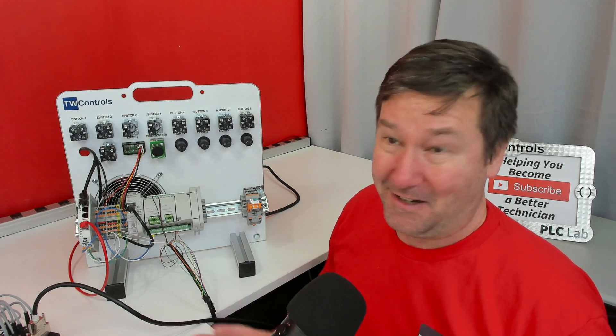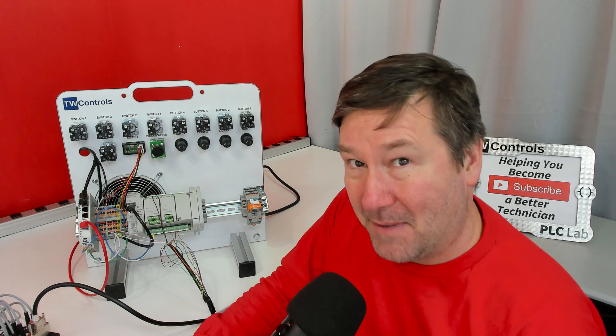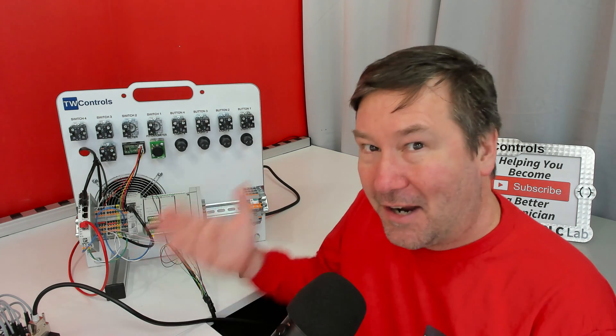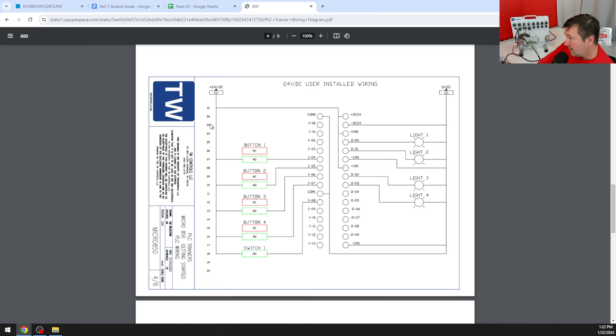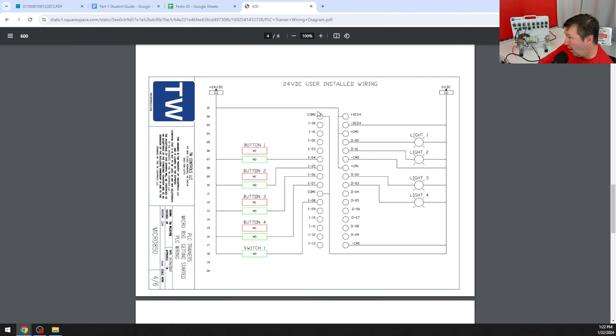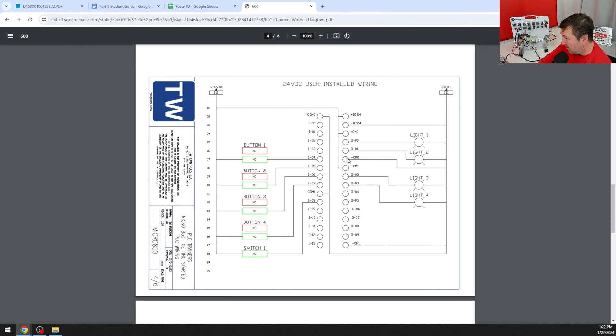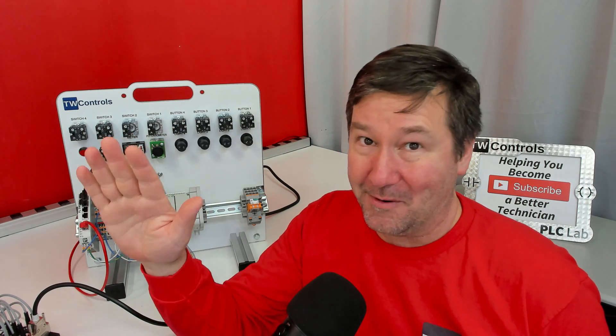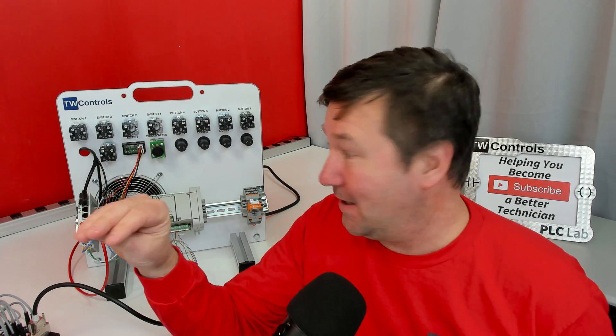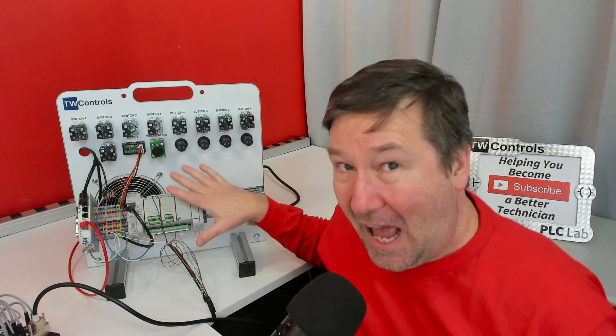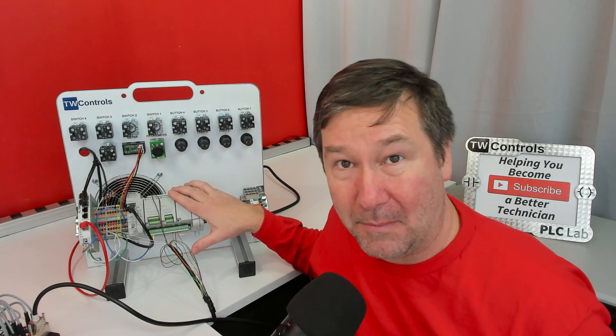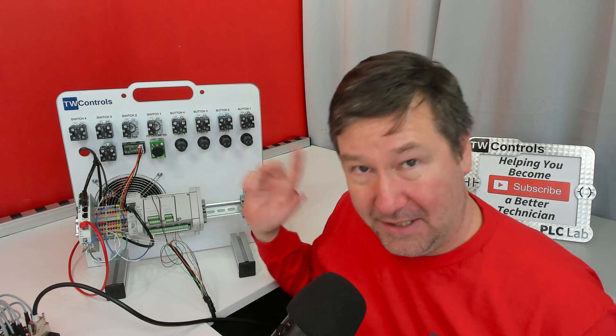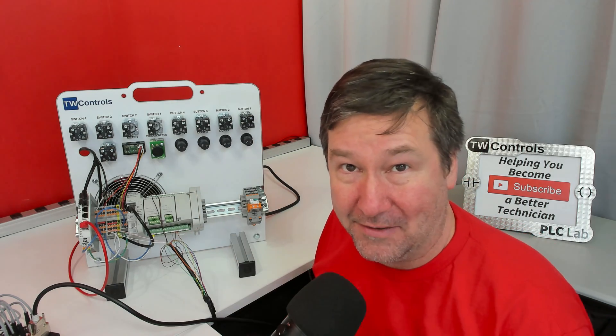But it does not take care of our wiring. If you've watched enough of my videos, you know now we're going to ask, do I have current? And we absolutely do not because we're taking positive power to input 0 and input 1, but we don't have that return path. So we are going to take COM 0 and COM 1 to the minus of our power supply. That is the right set of terminals. And we're also going to take our minus CM 0 and minus CM 1 to the 0 volt. And then we're going to take our plus CM 0 and plus CM 1 to our positive. Now if that made your head spin, don't worry. We have a video that explains exactly how to wire up a micro 820 and it'll be in that playlist at the end as well.